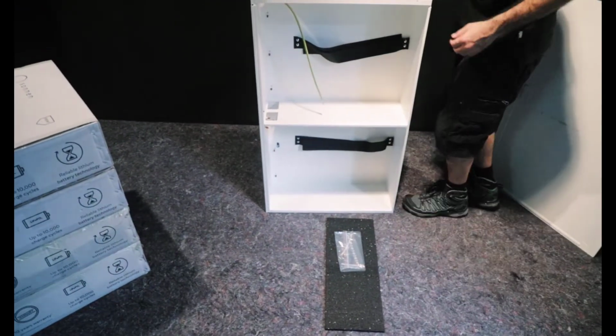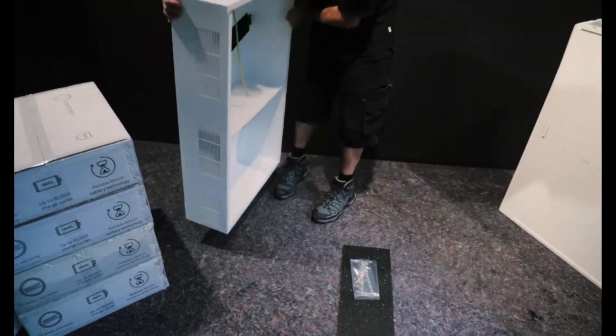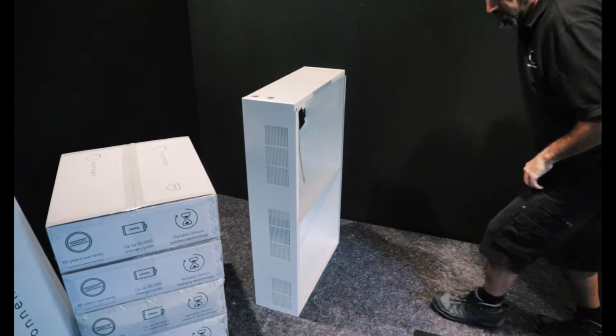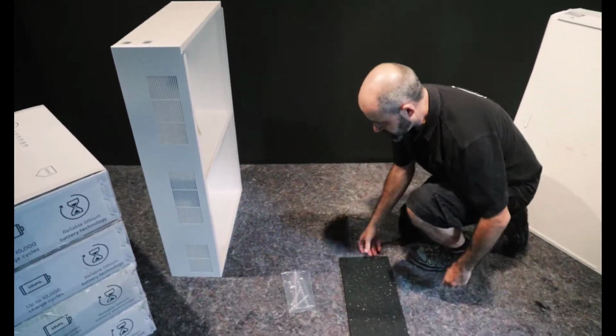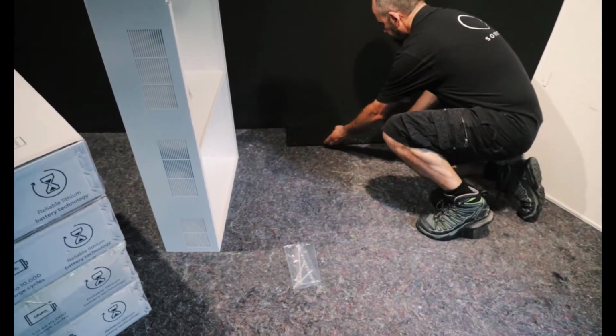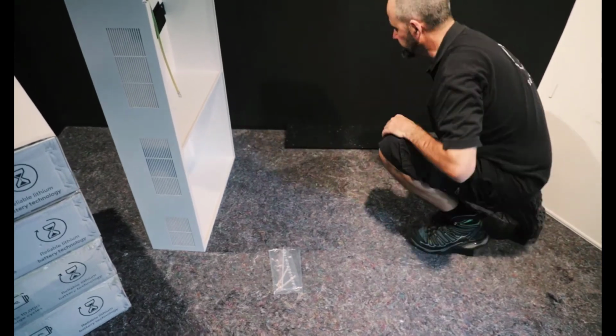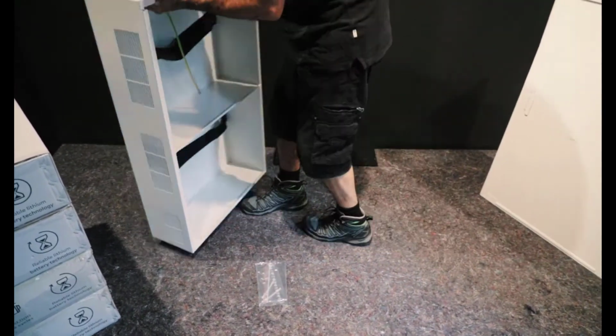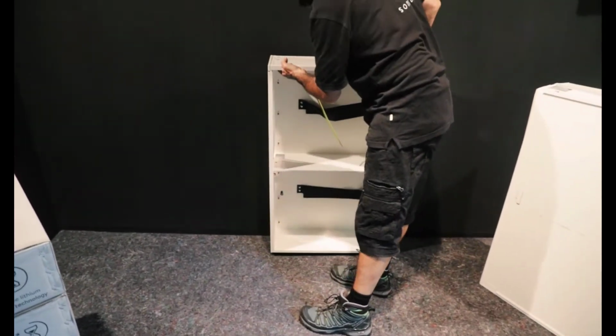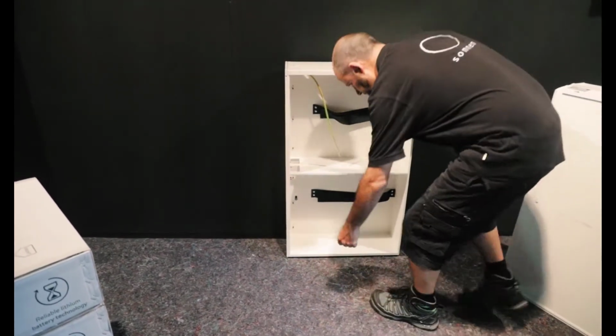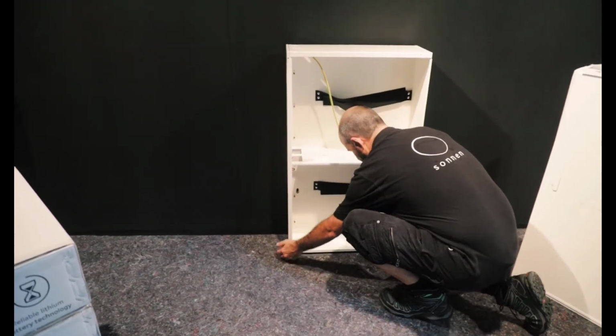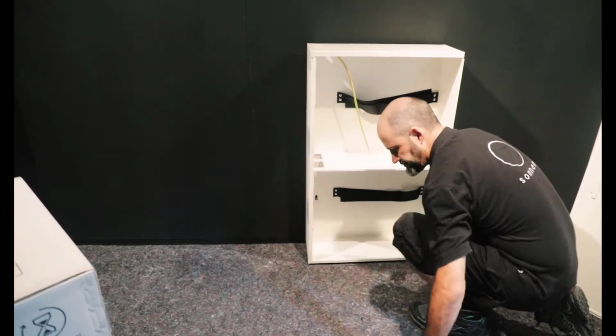Now with the main unit, there is actually a template to set out the position of these systems, but if you are using the extension housing, you don't necessarily need that. The self-leveling mat goes on first of all. This is to take out any slight undulations from the floor, but it also acts as a thermal barrier. The most important feature of that part of the product is the thermal characteristics to be a thermal barrier.